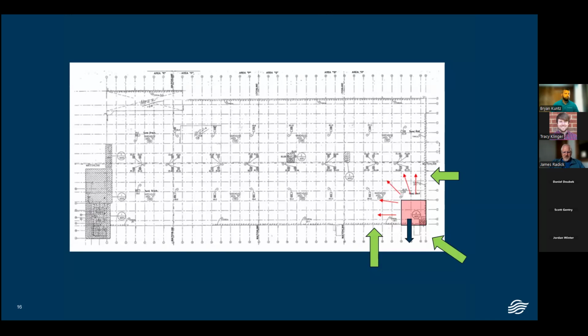So this next is just an image of that same facility that Brian was talking about. In that corner highlighted red, you can see a dark arrow showing the exhaust blowing out. And within that area, the red arrows are illustrating the migration of dirt away from there. Now, how could that dirt move away from there? Well, I've got a general negative, but I also have outside influences. Buildings are dynamic. If people are making money, you've got a dynamic building. There are things going on: production, doors opening, closing, etc.